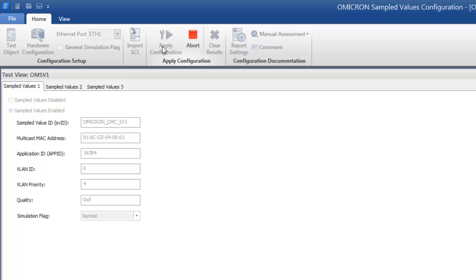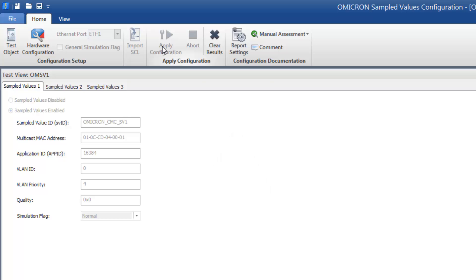From this moment on, the sampled values are published within the substation's Ethernet network, even if no test module is opened yet. Be careful, since publishing sampled values into an active substation network can have severe consequences. It can cause unintended results and also shutdowns.